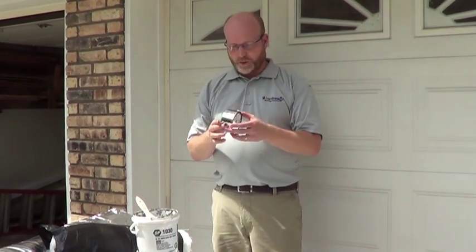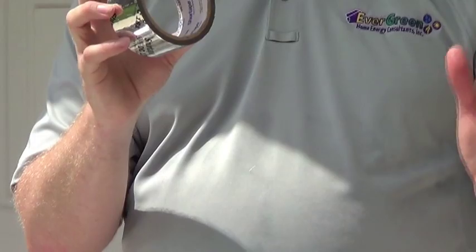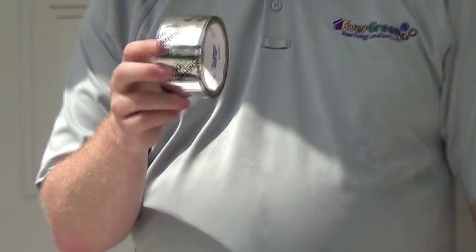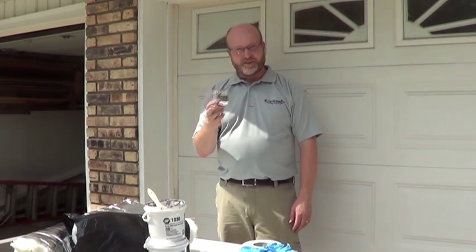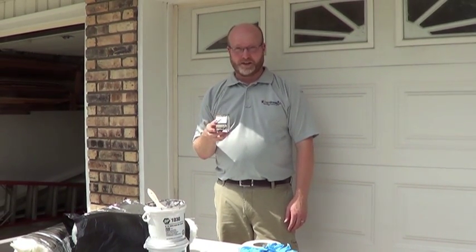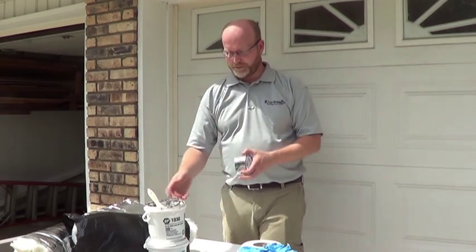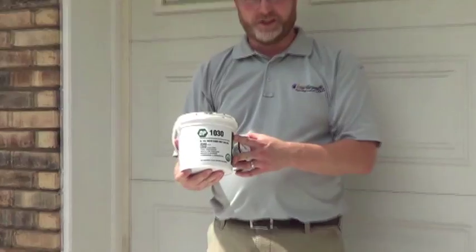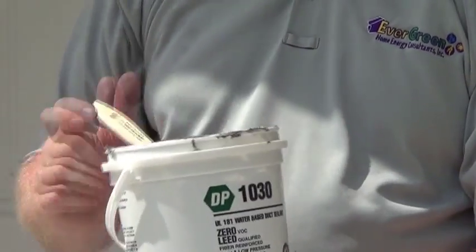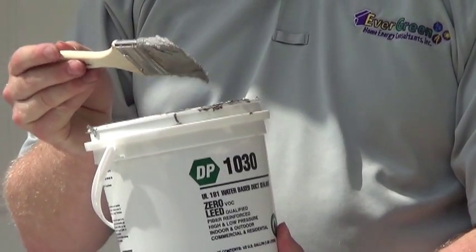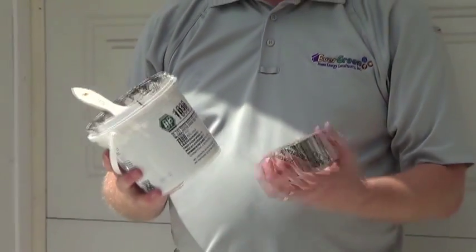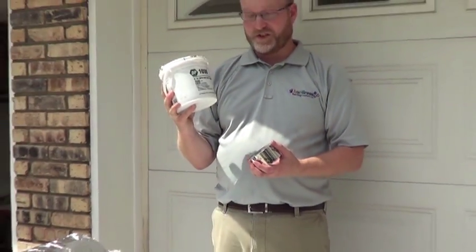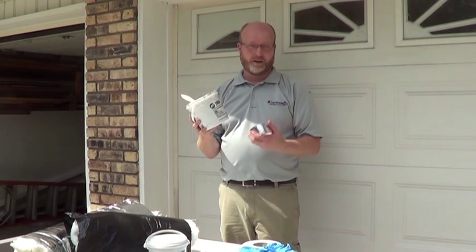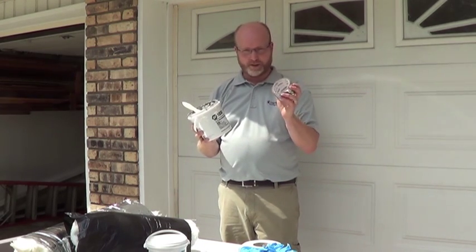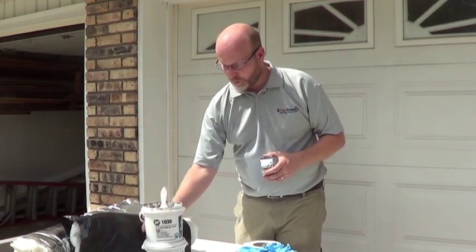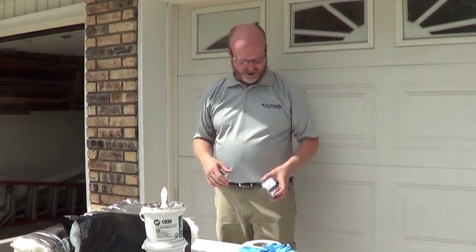Now, not too long ago we were using a lot of foil tape. Foil tape's not a bad way to seal ducts, but it doesn't last as long as some of the other products that we choose. At Evergreen Home Energy, we do testing on duct systems, and we've tested systems that use tape. We've tested systems that use mastic like this. This is called duct mastic. It's water-based, and it goes on like a paste, like with a chip brush like this. And in those tests, we have found very simply that systems that were sealed using duct mastic passed much quicker and with a lot more tolerance than the systems that were using only tape. So we know the duct mastic works well, it's long lasting, and does a great job.